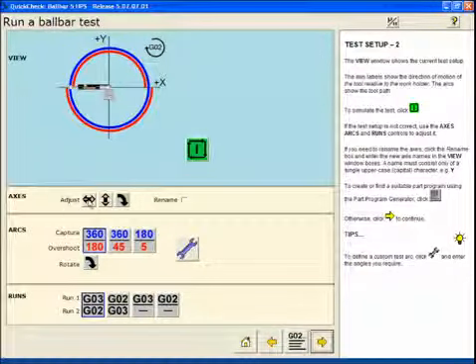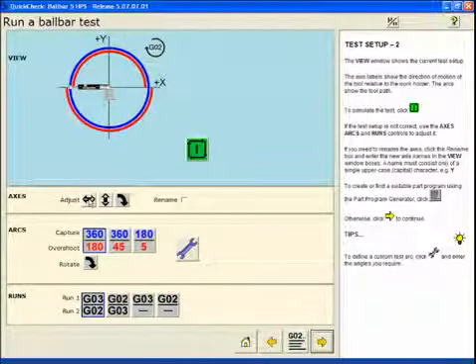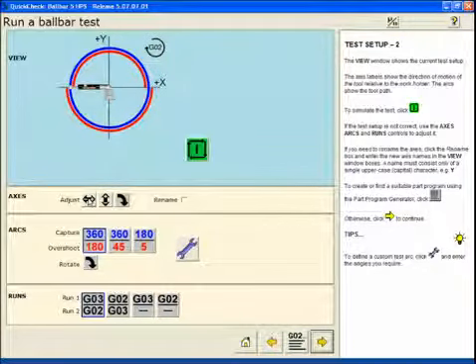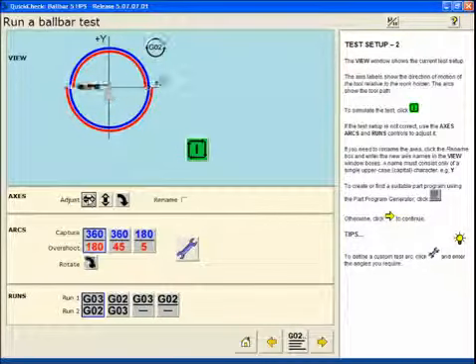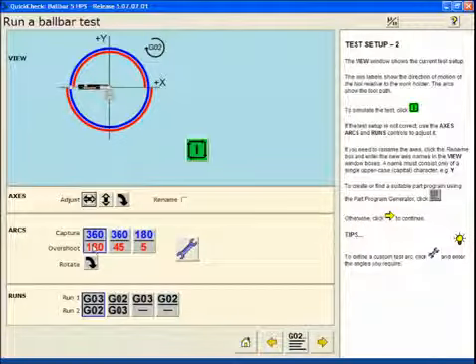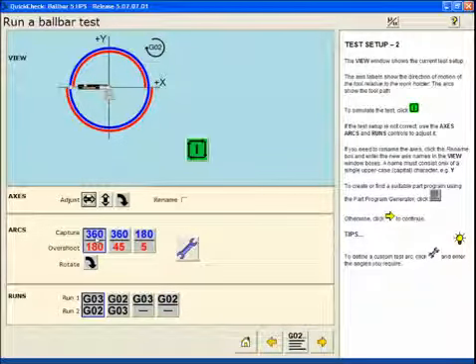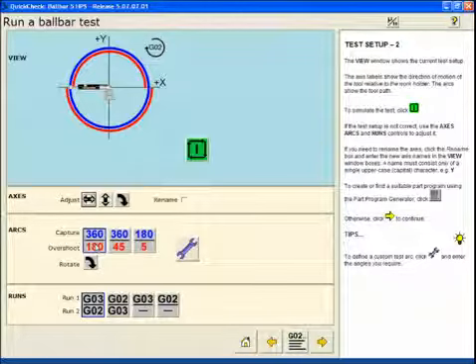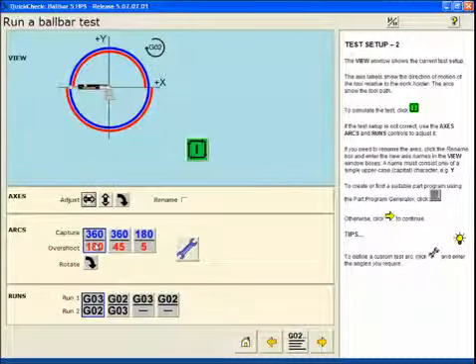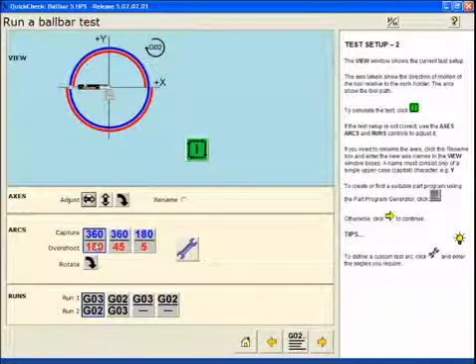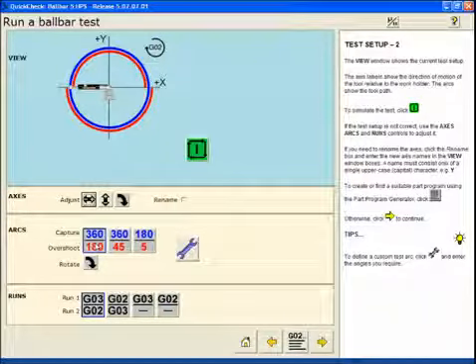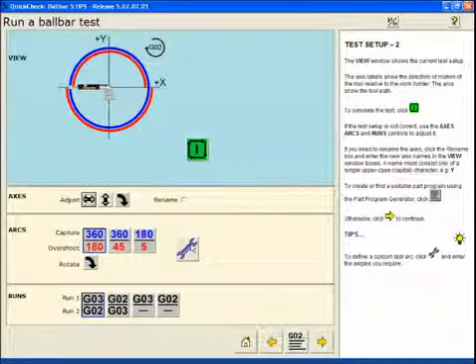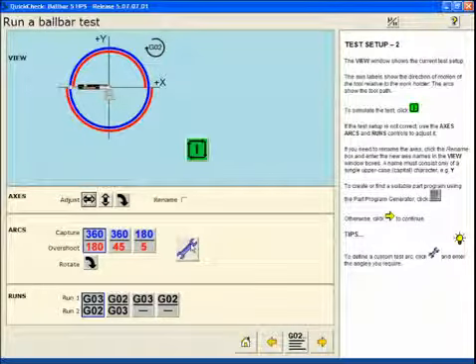Here we can set up the axis nomenclature to make sure that it corresponds to the machine that we're using. Select the axis labels. We're going to set up data capture of a 360 degree data capture and a 180 degree overshoot. The overshoot is the travel that the machine moves through prior to collecting data and after collecting data. We can adjust this using the configuration tool if one of the selections don't fit our need.